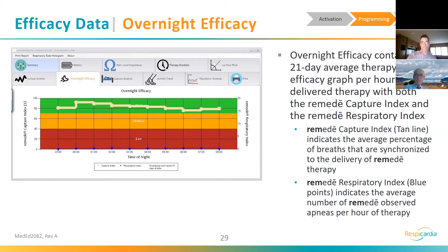In the case where we don't see such a glowing report here, we'll want to dig in more deeply into the capture analysis trends. This is where we see the effectiveness of stimulation in each of the different sleeping postures, or positions, rather. This first trend is giving us insight into all positions, and is where we start. On the lower scale, we see our current levels, and that tells us at what current levels we are becoming effective with our stimulation.